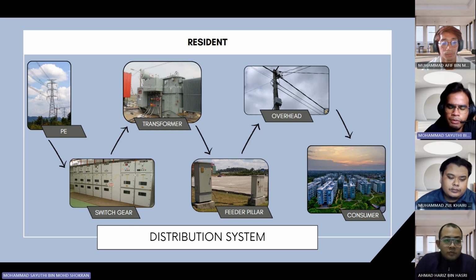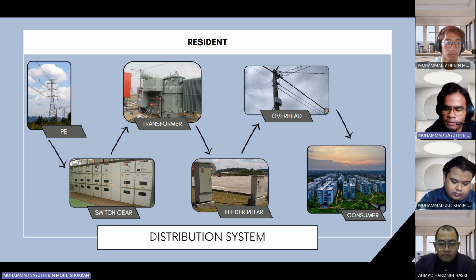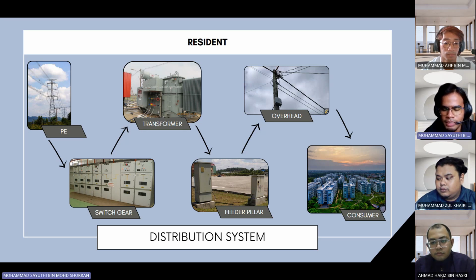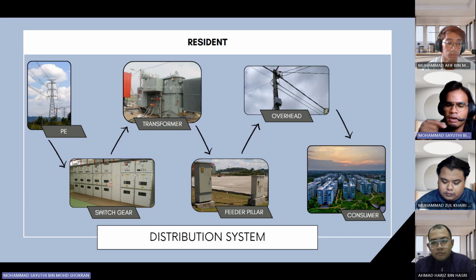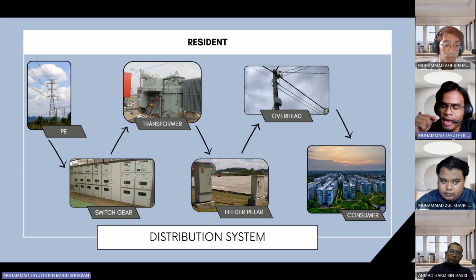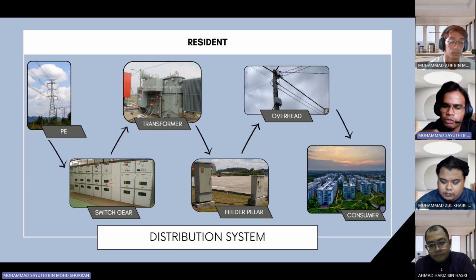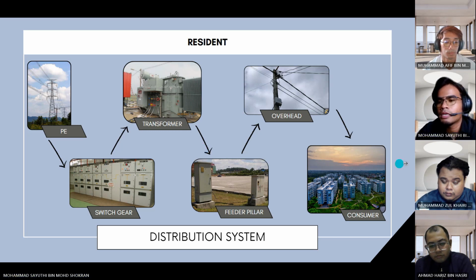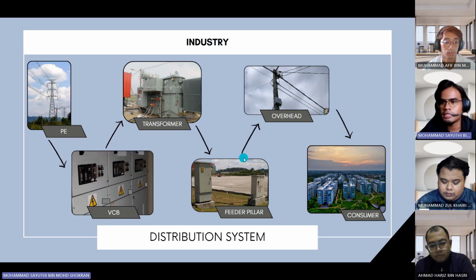The RMUs also offer flexibility in terms of configuration and expandability. They can be easily expanded by adding more modules or units, allowing for future system modification or extensions. And for the cost, switchgear generally has a lower upfront cost compared to a VCB, vacuum circuit breaker. They are more economically viable for low to medium voltage distribution systems due to their compact design and simpler construction.